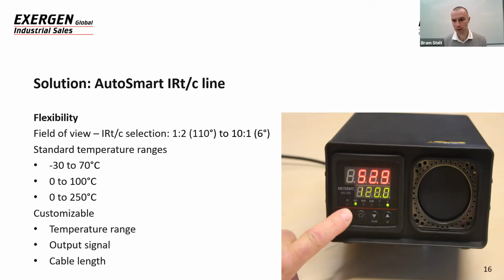You can choose the output signal. So the 4 to 20 milliamp and the 0 to 10 volt are standard. You can always, any AutoSmart has these standard as output signal, but you can also choose 0 to 20 milliamp, 0 to 5 volts, 0 to 2.5 volts, 0 to 1 volt. We are working on digital solutions. We hope to present that later this year. And you can basically connect any cable length to the AutoSmart transmitter to meet the needs and the demands of the customer.